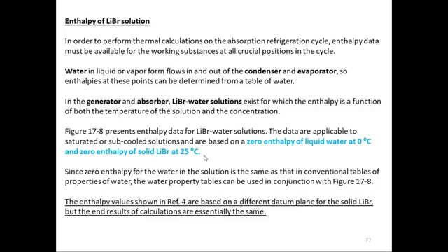If you change this datum line, zero enthalpy at 0 degrees centigrade is also used in the steam table. So we don't want to change it, but this lithium bromide zero enthalpy at 25 degrees centigrade can be changed. Some other books have similar charts, but their charts will look different because their datum line for the lithium bromide is different. That's why. So this is the Stoecker that we are talking about. Stoecker is using 0 degrees for water for 0 enthalpy and 25 degrees for lithium bromide for 0 enthalpy.